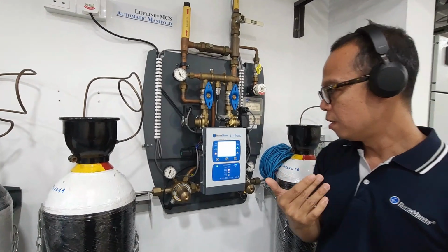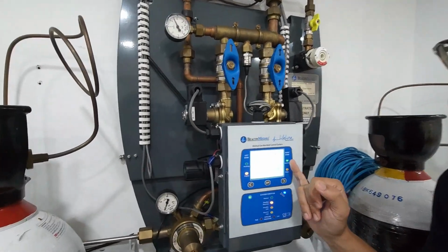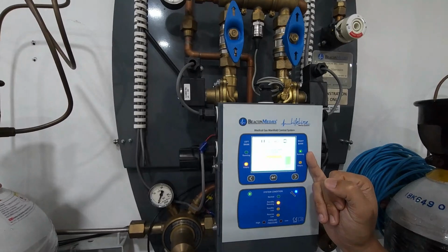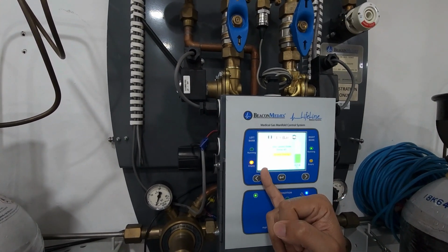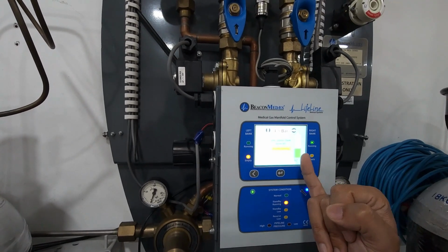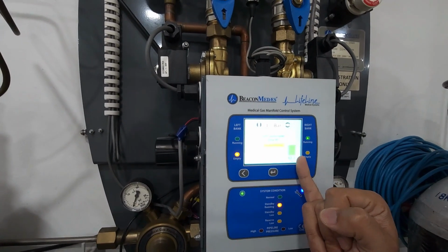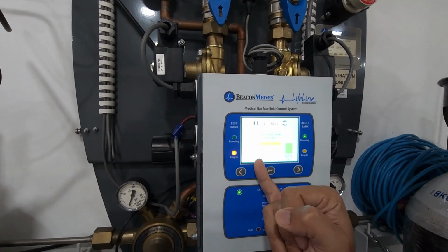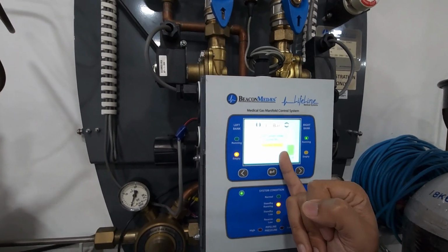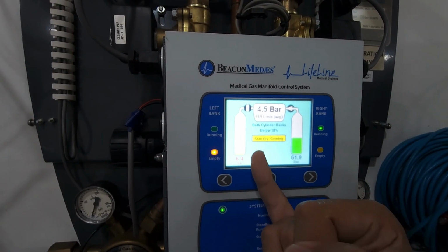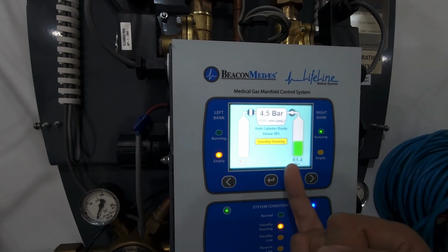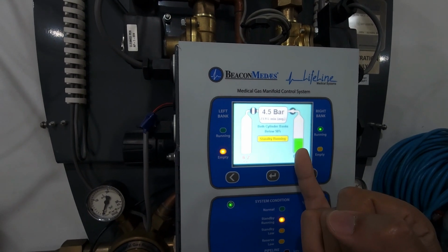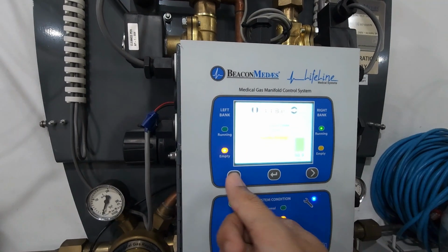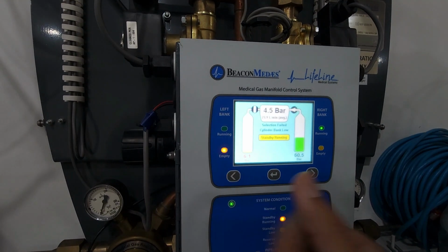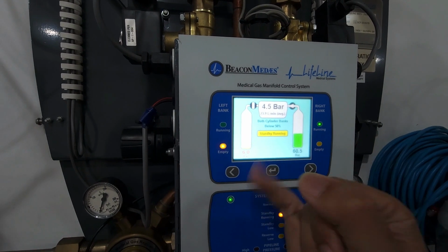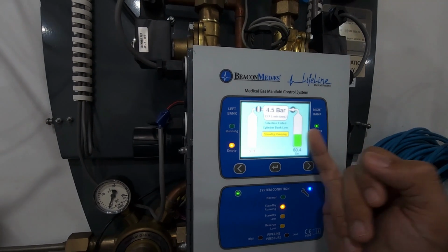Okay, if you come closer and look at the screen, you have an indication of pressure remaining on the right bank and pressure remaining on the left bank. As you can see here, the manifold is running on the right side because that's where the gas is available. But on the left side, it's empty. Right now, there's an alarm that says standby running to alert the engineers to fill up the left side of the bank. And there's a safety feature on the Lifeline manifold where you can't switch from this bank to this bank when this is empty. If I click this one, trying to switch to the left, it can't. It says selection failed, cylinder bank is empty. So this is a safety feature to make sure of the continuous gas supply running to patients.